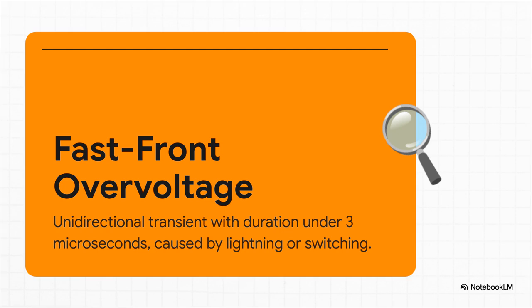The sheer danger here is the absolute speed of the energy transfer. It can cause immediate, severe, and often completely irreversible damage to your electrical equipment, like insulators and transformers. To put that speed into perspective for a second, just look at this number: 3 microseconds. That's it. A fast front overvoltage typically completes its entire total duration in fewer than 3 microseconds.